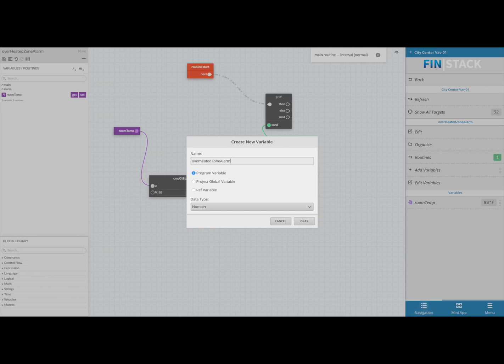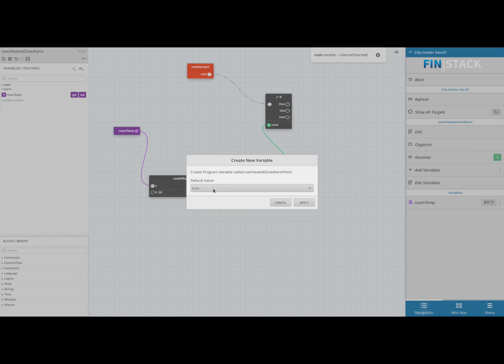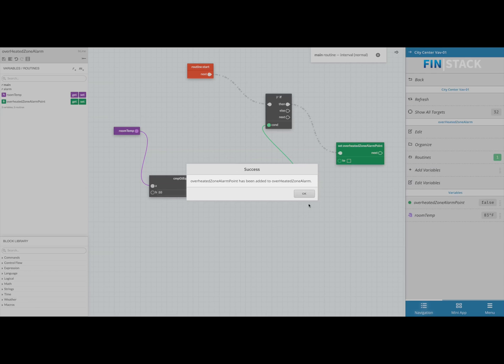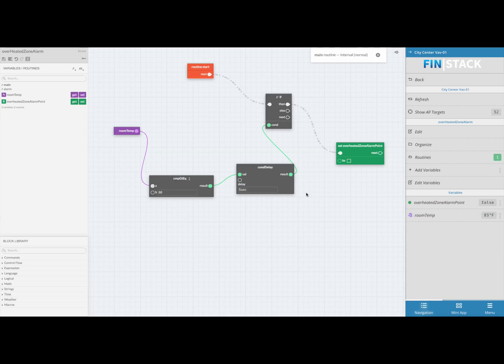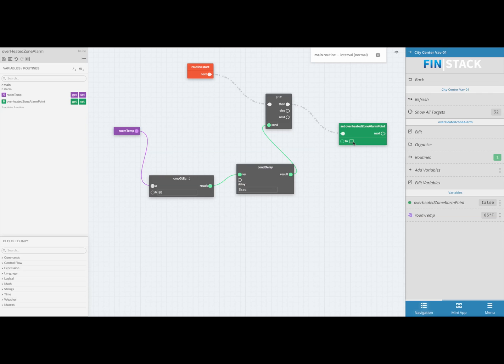In this menu you can name the variable and choose what type of variable this will be. Make sure to make it a boolean point as we will need it to turn on and off to trigger the alarm. Next they will ask you what you'd like the default value to be, and in this case I'm going to select false. Once you're done hit okay and it will automatically create a set block with your new variable. The checkbox at the very bottom of the set block determines whether you're setting the point to be true or false, so for this one I will check the checkbox so that if our condition is met the point will turn on.